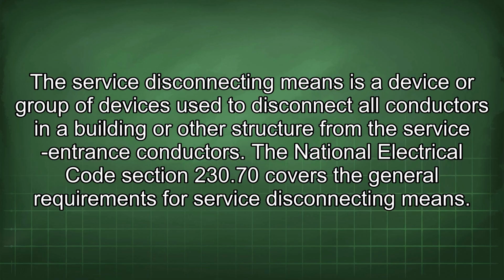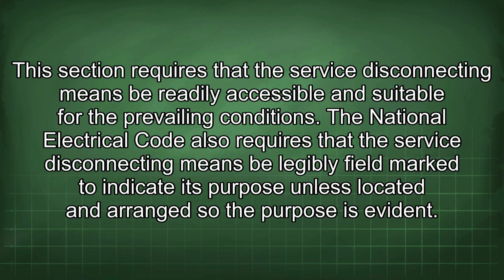The National Electrical Code Section 230.70 covers the general requirements for service disconnecting means. This section requires that the service disconnecting means be readily accessible and suitable for the prevailing conditions. The National Electrical Code also requires that the service disconnecting means be legibly field marked to indicate its purpose unless located and arranged so the purpose is evident.